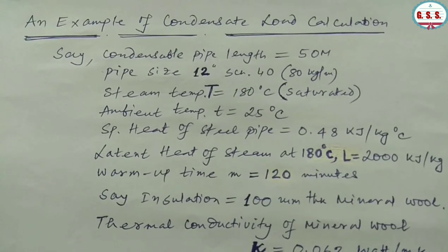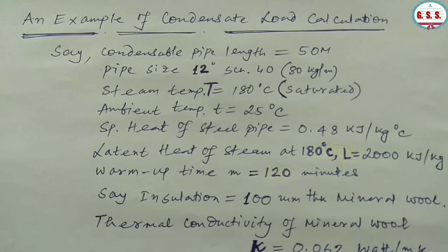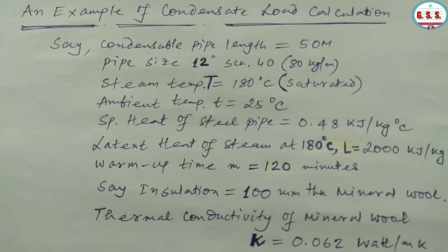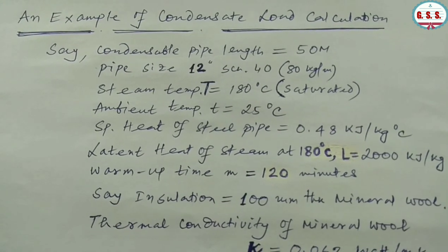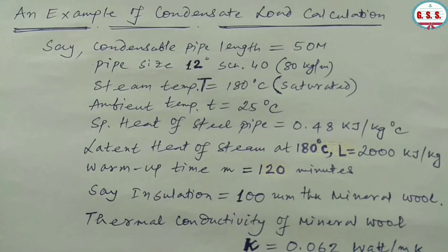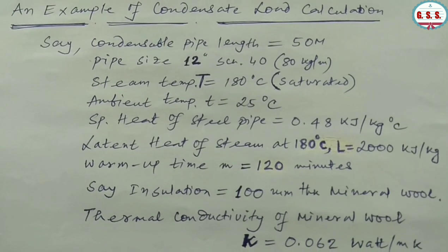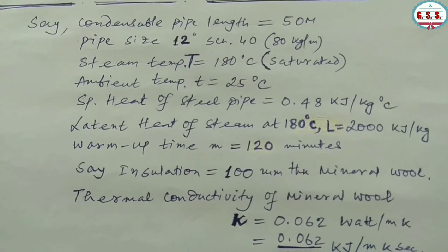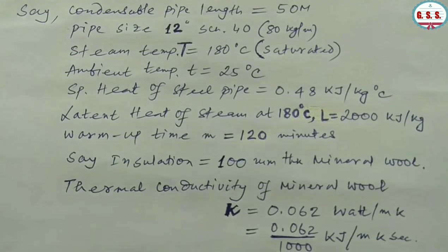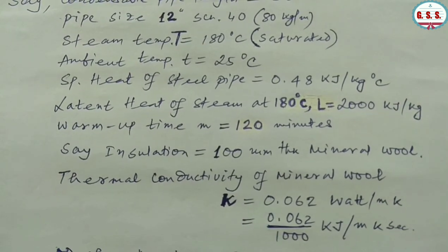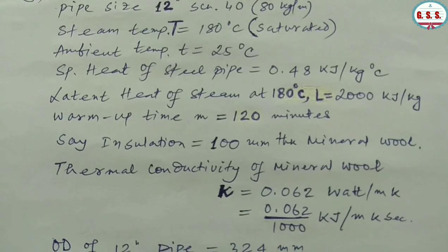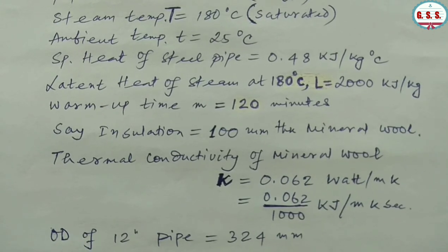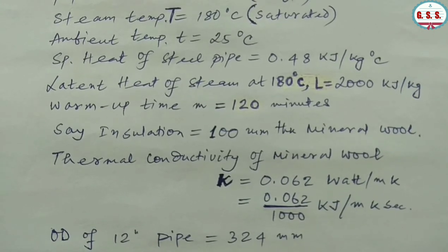Now let us take an example of condensate load calculation. Condensable pipe length = 50 m. Pipe size is 12 inch schedule 40, so pipe weight = 80 kg/m. Steam temperature T = 180°C (saturated). Ambient temperature t = 25°C. Specific heat of steel pipe = 0.48 kJ/(kg·°C). Latent heat of steam at 180°C, L = 2000 kJ/kg. Warm-up time M = 120 minutes.